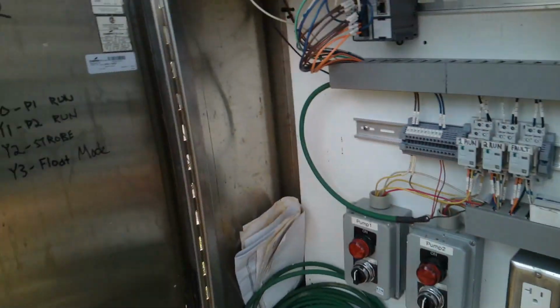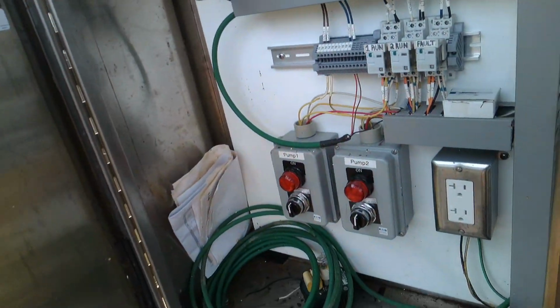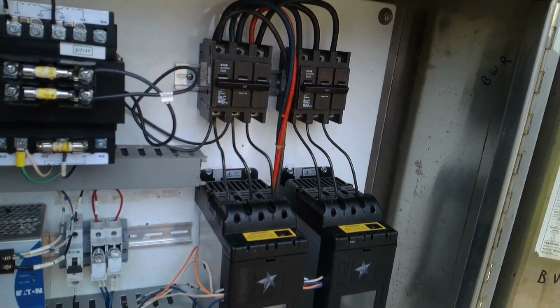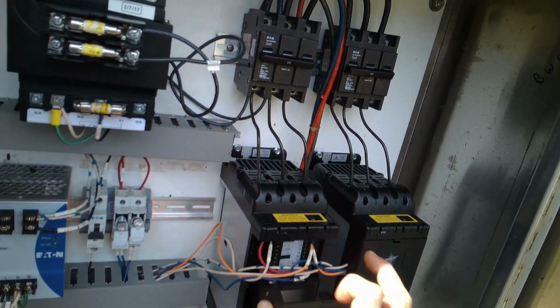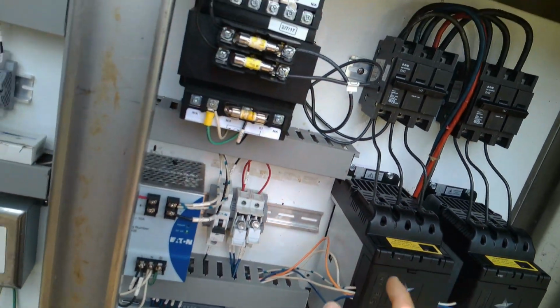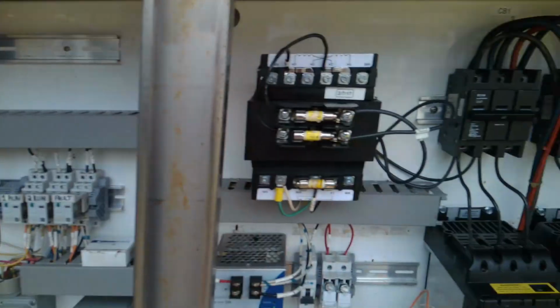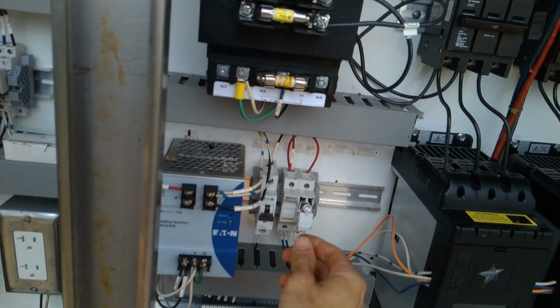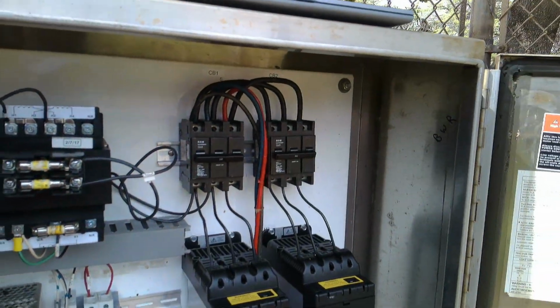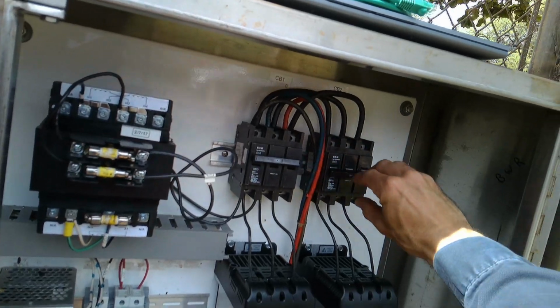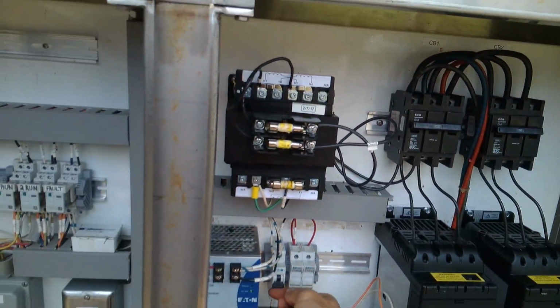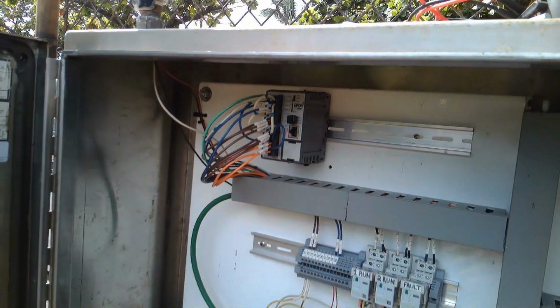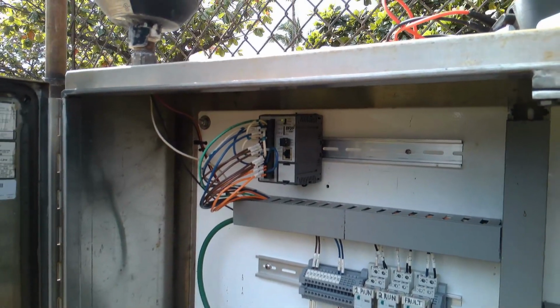I don't have a wiring diagram, that's just panel specifications. Let's see. DC1. So DC1 right here runs the PLC and the soft starters. I checked those fuses for continuity. We don't have any blown fuses or anything. I think we're safe to power up. Let's go ahead and give it a shot. And then this should wake up the PLC. There's the blinking lights. That's good.